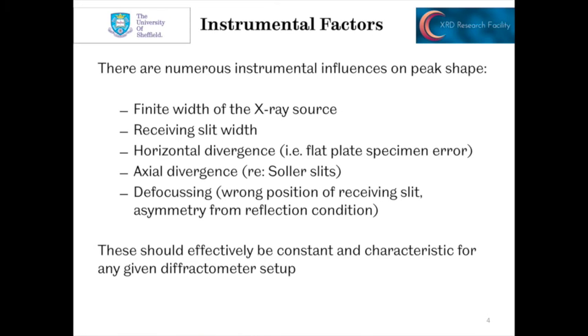But these should be effectively constant and characteristic for a diffractometer. So if we're not changing the setup of the machine, these factors should always be the same. You should at least be able to compare like with like.